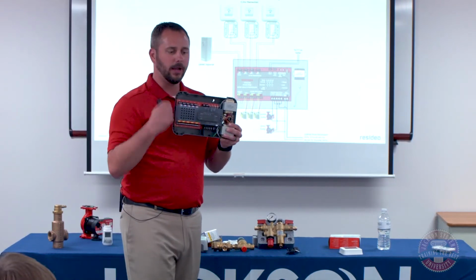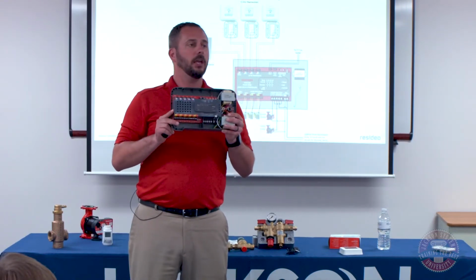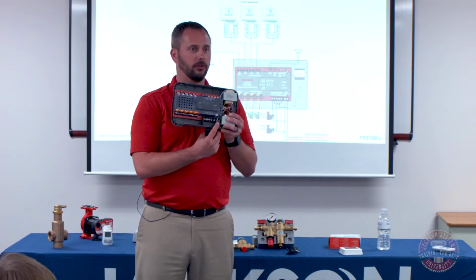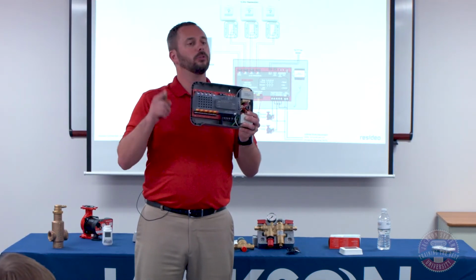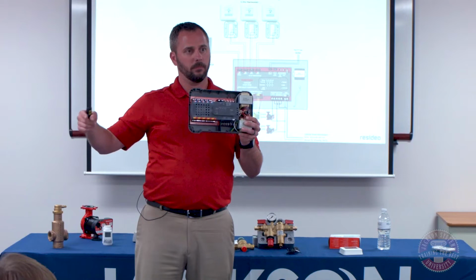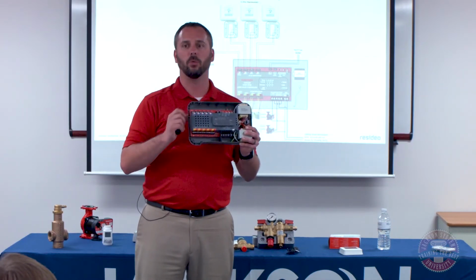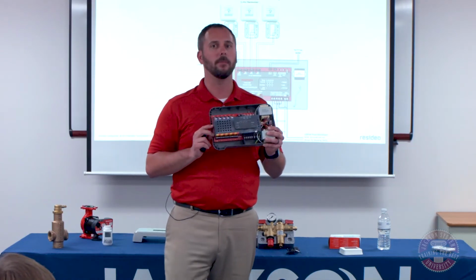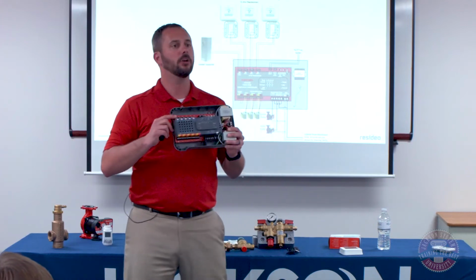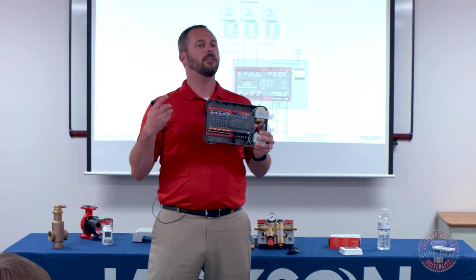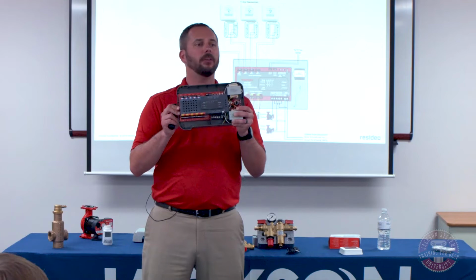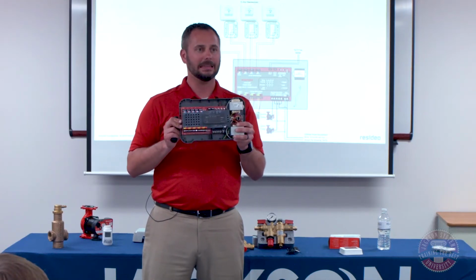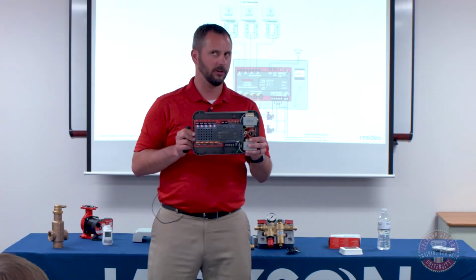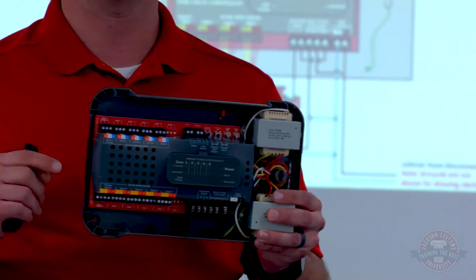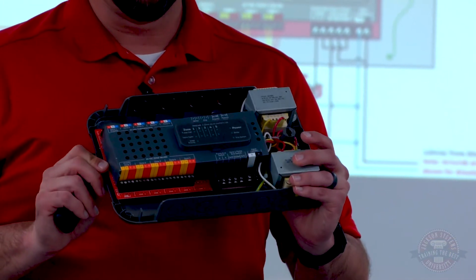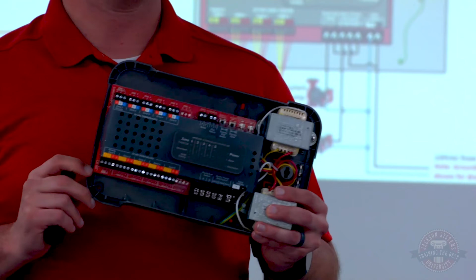We can do domestic priority as well, but if you need to wire the pump terminals in here, you're going to lose a zone on every panel, because you're going to sacrifice one. And I've got some wiring examples here in a minute that show that, but you're essentially sacrificing one. So if you had 10 zones, you would need to buy zone panels with the capacity of at least 11. I said 10 zones, so 11 zones, because you're going to lose one zone as a jumper. But yes, you can ultimately expand these indefinitely.